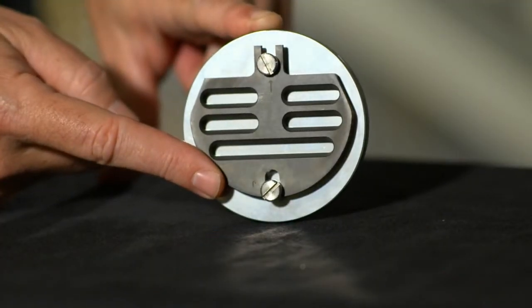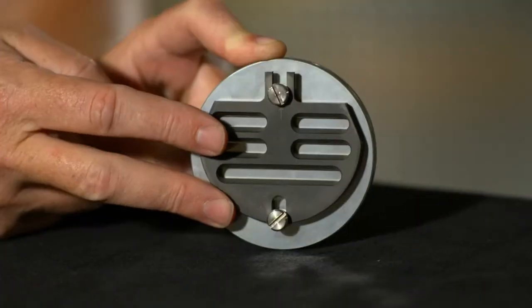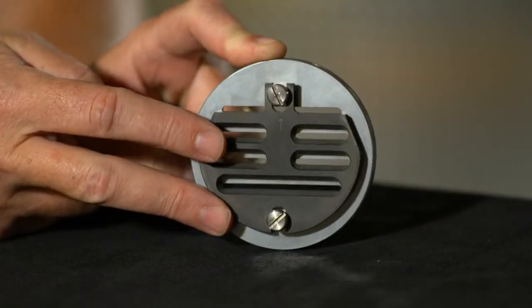There's a very short stroke, which makes for more accurate regulation and less droop. It features a multiple orifice design. The disc and plate are in constant contact, so you have no valve chatter.